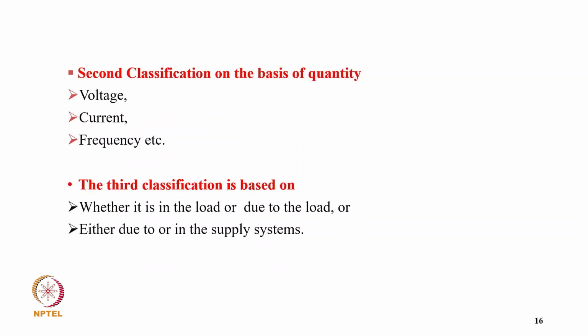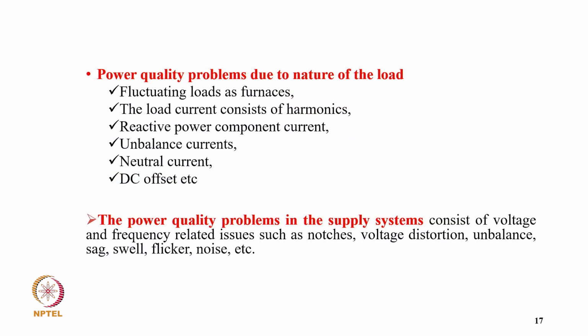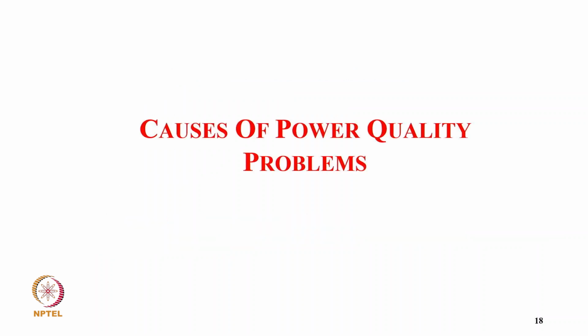The second classification, on the basis of quantity, is voltage, current, and frequency, etc. And the third classification is based on whether it is due to the load or in the supply system. Power quality problems due to the nature of the load come from fluctuating loads such as furnaces. The load current consists of harmonics, reactive power component current, unbalanced current, neutral current, DC offset, etc. And power quality problems in the supply system consist of voltage and frequency related issues such as notches, voltage distortion, unbalance, sag, swell, flicker, noise, etc.